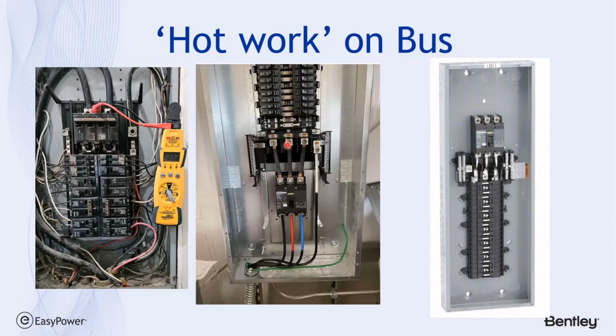Now you say, well, the National Electrical Code just required a cover over the incoming conductors for the termination to prevent inadvertent contact. Doesn't that count? So the answer is no, it's not good enough. Here's an example of a piece of plastic that covers the incoming conductors to this main breaker, and it will reduce considerably the potential for accidentally touching these phases without knowing it. But it's not an arc barrier, so this doesn't cover it as far as incident energy protection.